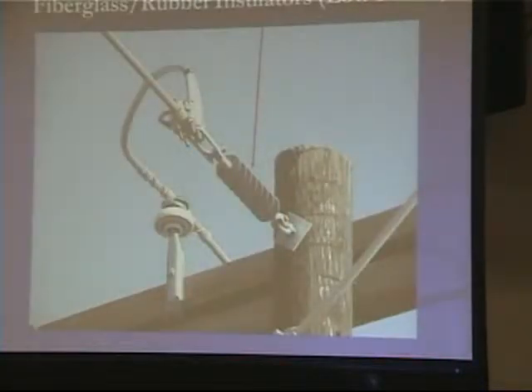I keep trying to get them to buy more clips. When they run out and don't think about it, they don't use them anymore. So then I tell them, if you can't do the clip, replace that with a better insulator. I think I've got a picture of those coming up. The fiberglass rubber insulators are basically noise-free, I call them, because very few times do we ever have RF noise coming from those. They're pretty sturdy little devices, and we hardly ever find problems with those.